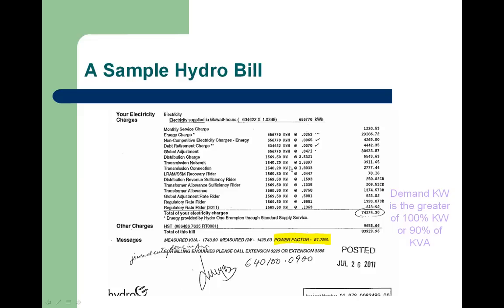So in a case like this, to increase our power factor to 90%, we would have to put in enough capacitance so that 90% of our kVA equaled something less than 1,425 kilowatts.